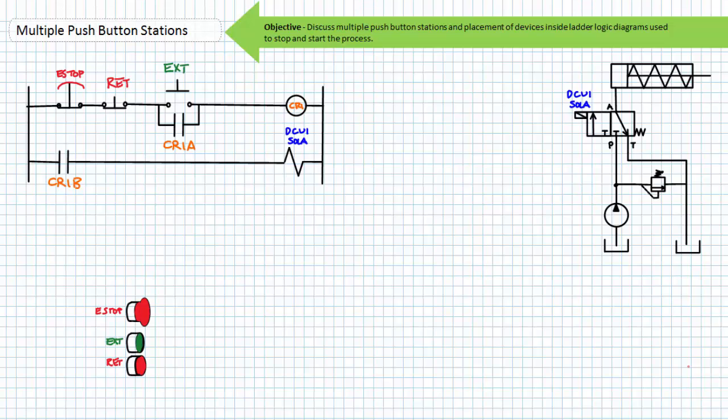Ideally, all the push-button stations should perform the same function, the only difference being their different locations. The methodology is surprisingly simple: devices that stop the process go in series with each other, and devices that start the process go in parallel with each other. Consider this three wire control circuit controlled by a single push-button station consisting of a maintained e-stop, a momentary retract, and a momentary extend push-button.